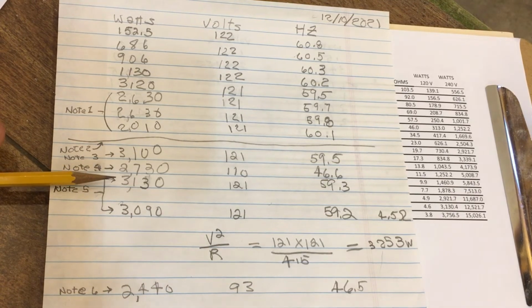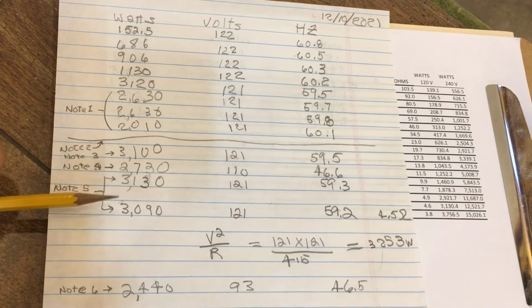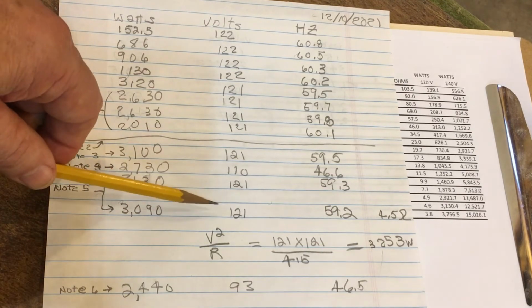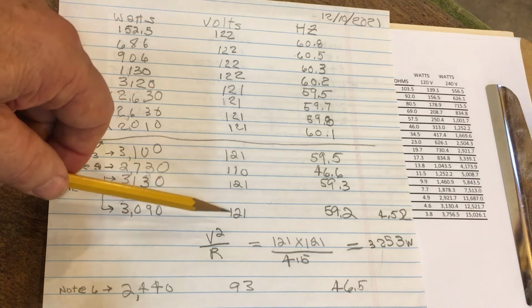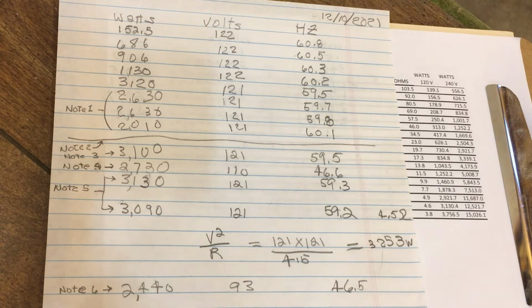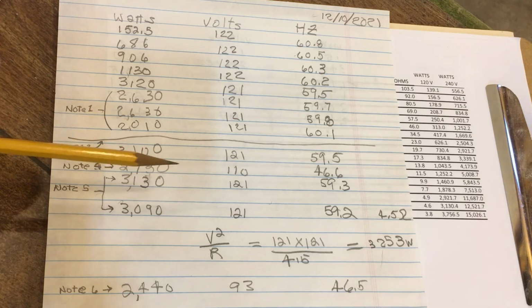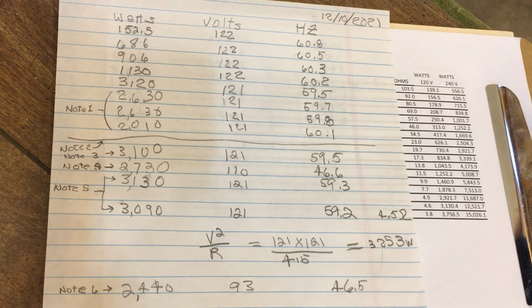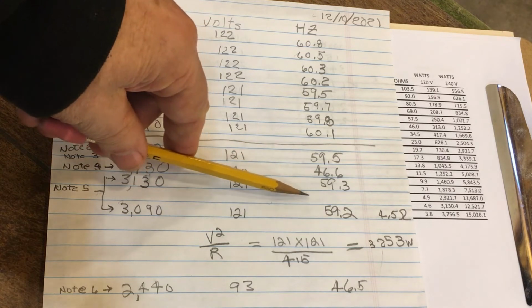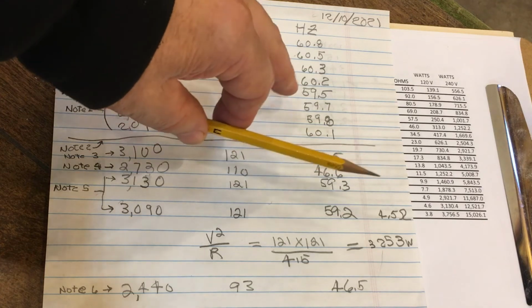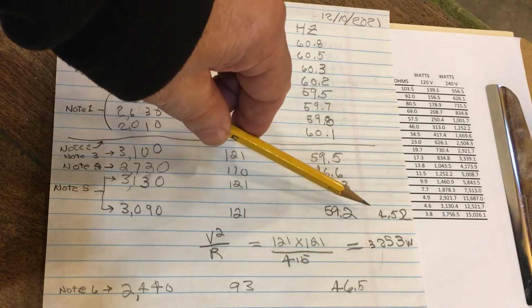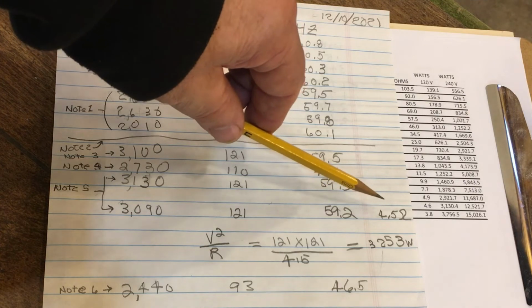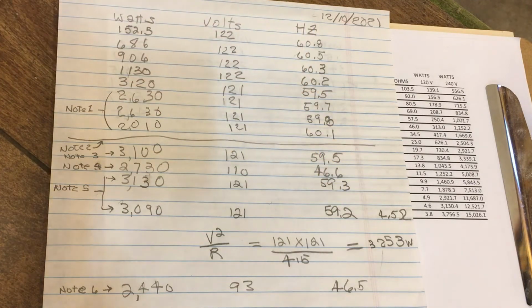And at this time, I was scratching my head trying to decide what I wanted to do next. Apparently, I took the power off, and then I decided to turn the power back on. This time, the voltage measurement was not a reading off of the power monitor, but was obtained using a multimeter. Again, the frequency was looking good, and this time I shut the generator down and then measured the DC resistance at the terminals to the load bank, and that came out to be 4.5.